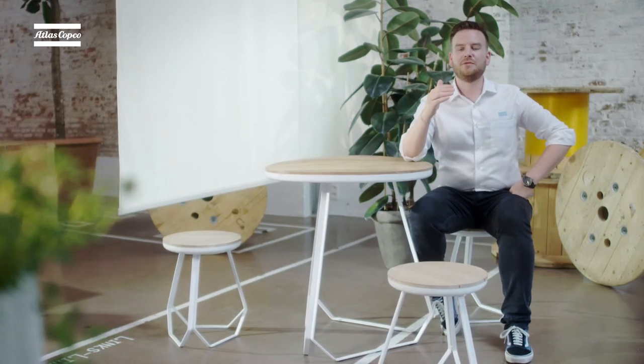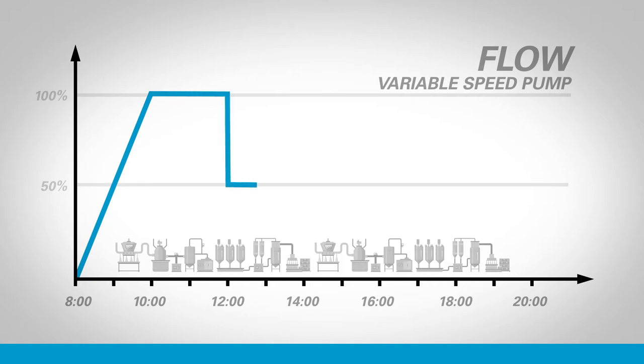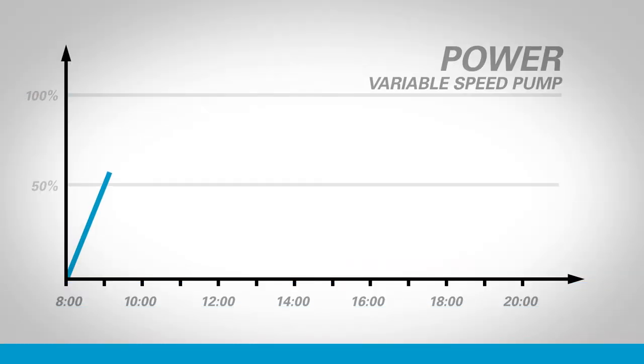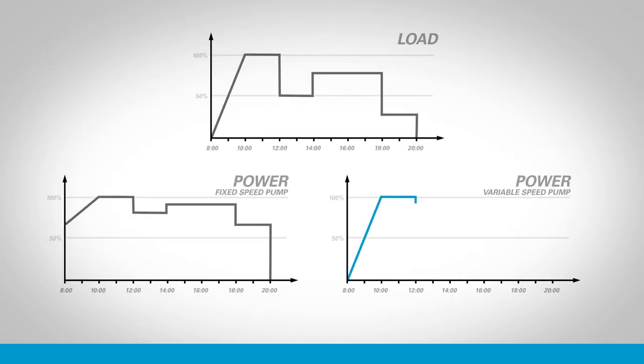Now let's look at a similar diagram for a variable speed unit. We want the load to be identical. This time, instead of plotting a fixed flow rate, we're going to set the vacuum level at the maximum authorized pressure — we take the pressure closest to atmosphere and fix the pump to pull that vacuum level all day long. Now we can fill in the flow rate: when we have maximum load the pump speeds up to provide full capacity, and when the load is reduced the motor slows down accordingly. With a variable speed pump, the power usage is directly related to the speed and throughput of the pump. When the pump handles maximum load the power absorbed is the same as the fixed speed unit. When the load reduces by half, the pressure set point is maintained by the pump slowing down and as a result the power will also halve. At the extreme, when there is no load the pump will stop and consume zero power.